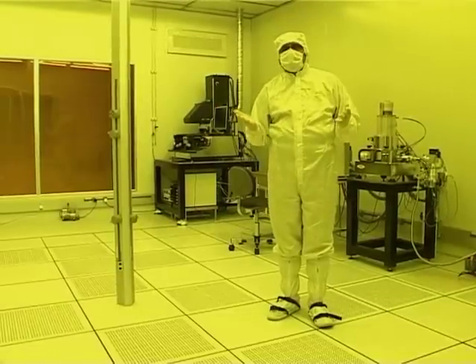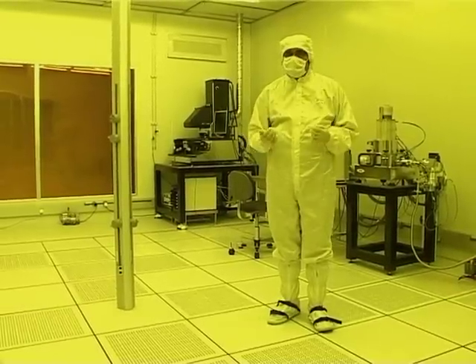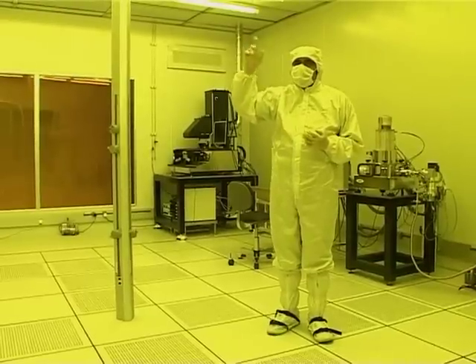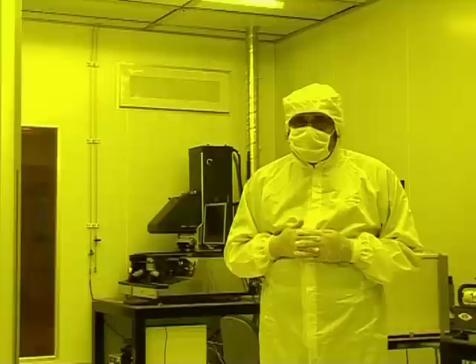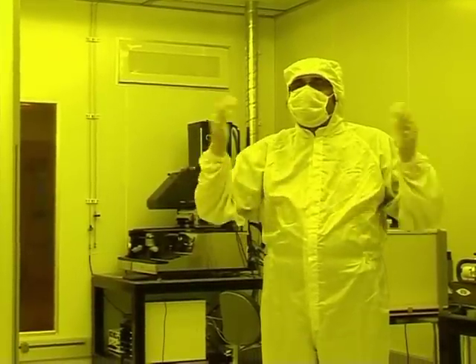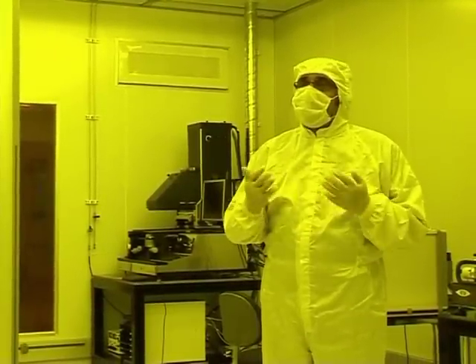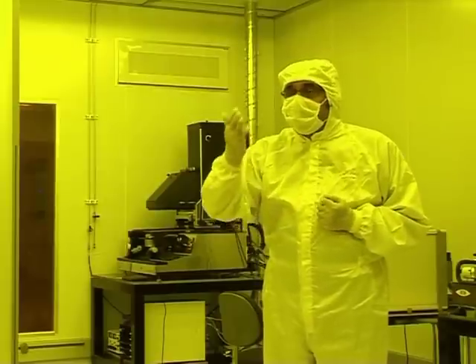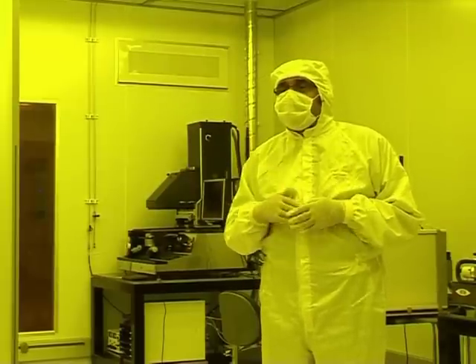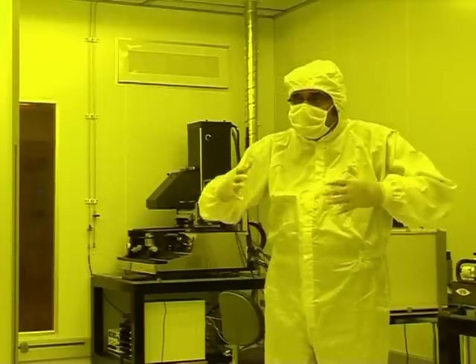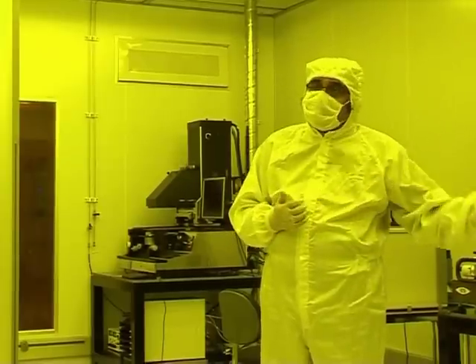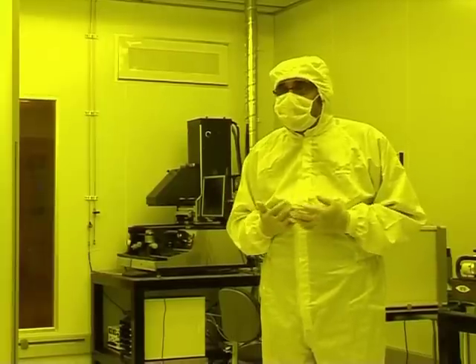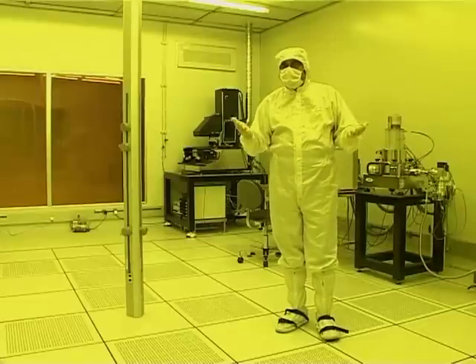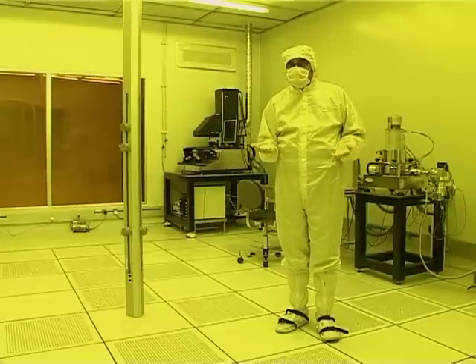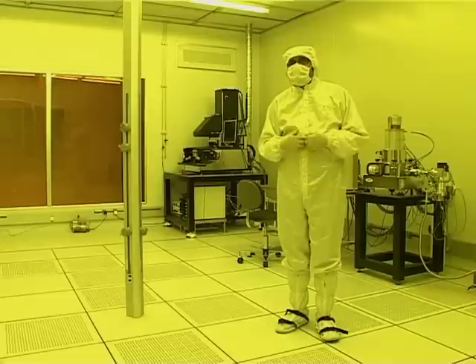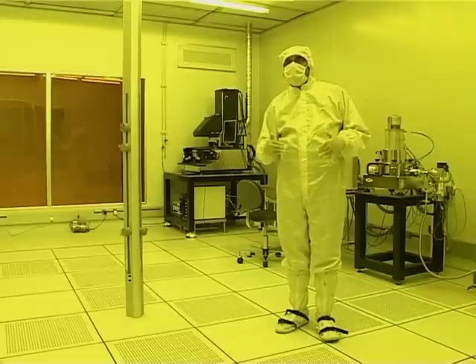Now, what distinguishes a cleanroom HVAC from the conventional system? First of all, you have fan filter units that arrest the particles from entering this room. And the second thing is the number of air changes per hour. In this room, we have more than 400 air changes per hour, whereas a conventional HVAC which we use at our house has 2 to 5 air changes. And also this room is pressurized compared to the outside. It is almost 30 Pascal higher than the outside pressure, whereas in your house you realize there's no pressurization within the room. So these are the things that distinguish conventional house air conditioning from cleanroom HVAC.